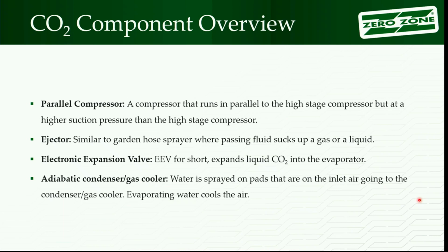Typically for us, I don't think we're unique in that, our lead compressors all have variable speed drives to try to trim the loads with that. And I think that's somewhat common in the industry. Then otherwise you'd have an ejector. An ejector is a device that uses the pressure differential you have, because we're talking big high pressures at flow rate, to move refrigerant, sometimes a liquid, sometimes a gas, from a lower pressure point in the system to a higher pressure point, gaining some efficiency.